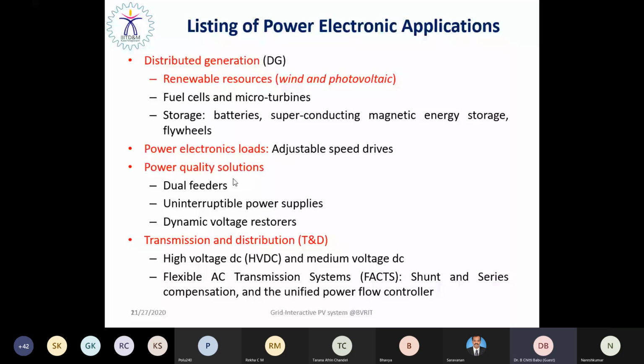We use HVDC transmission even for medium distance transmission with the help of underwater or undersea cable. We invariably use DC transmission. So we need to convert AC to DC at the sending end, and DC to AC at the receiving end. So we invariably use HVDC transmission, and we also use such devices in the transmission as well as in the distribution side to improve the overall system stability, as well as to improve the voltage profile at the point of common coupling whenever the transmission line is subjected to a fault. That is what the listing is, almost everywhere.